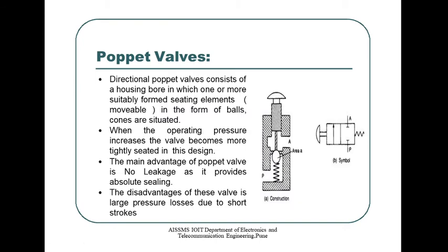Poppet valves: a directional poppet valve consists of a housing bore in which one or more suitably formed seating elements in the form of balls, discs, or cones are situated. When the operating pressure increases, the valve becomes more tightly seated in this design. The main advantage of a poppet valve is no leakage, as it provides absolute sealing. The disadvantage of this valve is large pressure loss due to the short stroke operation.